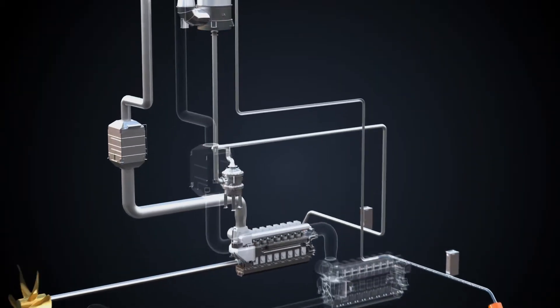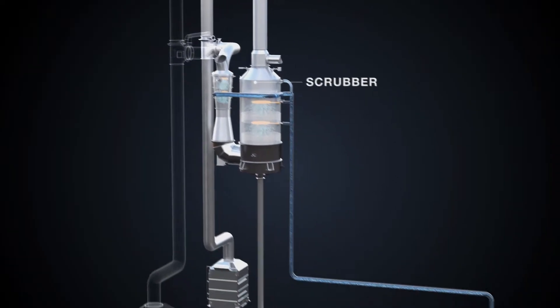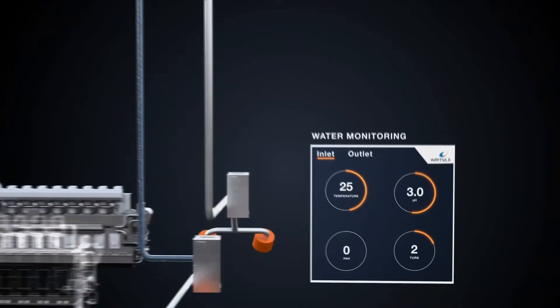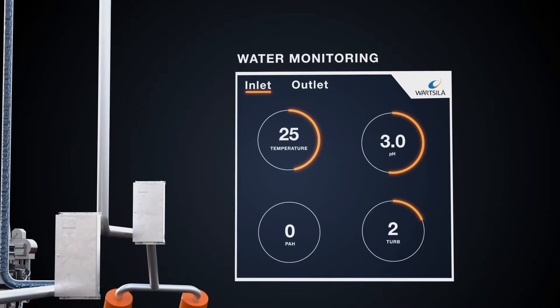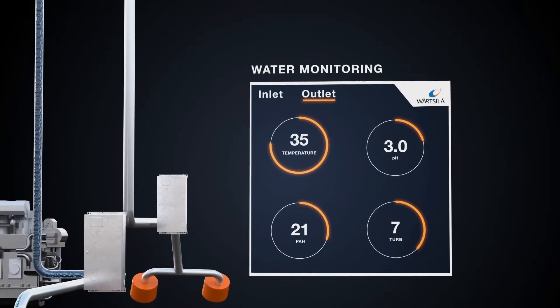Seawater is supplied to the system through scrubbing water pumps and then is routed to the scrubber unit. Both the inlet and the discharge of the wash water are monitored by the water monitoring unit. Our Wärtsilä pH Calculator will set the pH limit of the vessel required by the International Maritime Organization through a desktop exercise, eliminating the need for case-specific calculations or physical measurements 4 meters from the point of discharge.